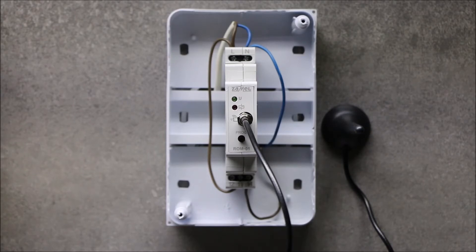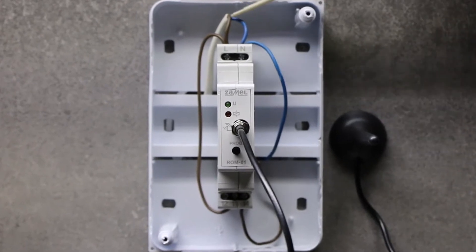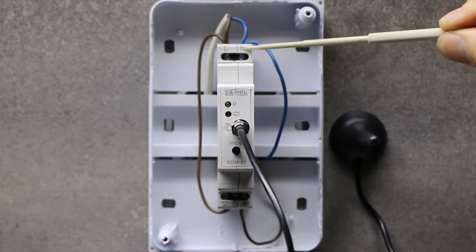Wires with a maximum cross-section of 2.5 mm squared can be connected to the terminals. Power supply wires L and N should be connected to terminals L and N of the receiver.